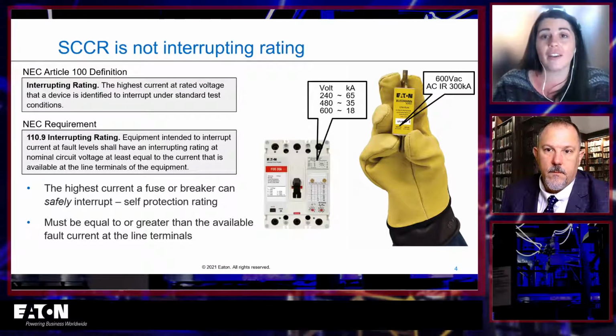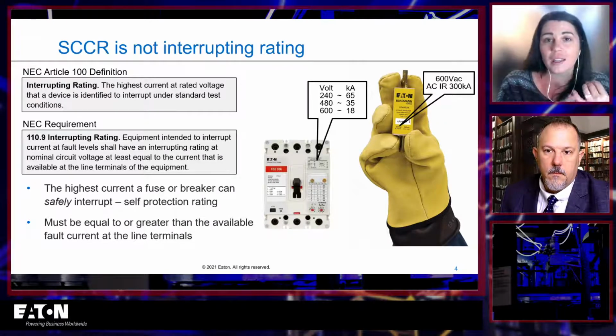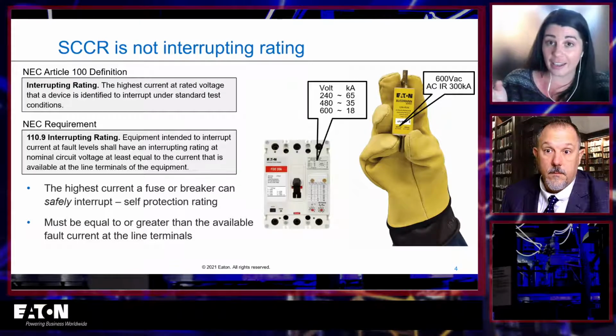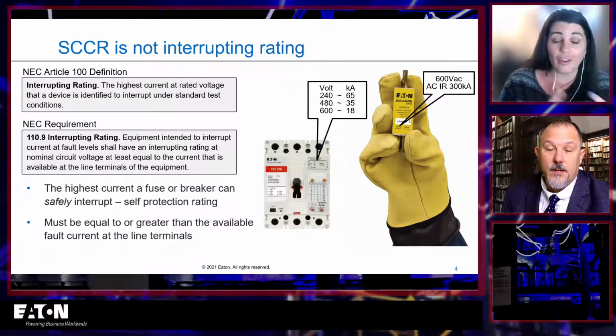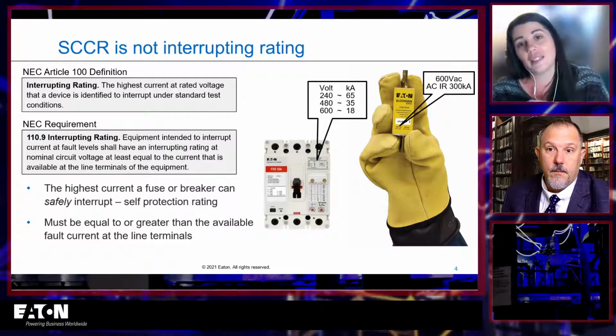Everything else, think of everything else in a panel. A bus, you think about a terminal block. What are they doing during a short circuit? They're sitting there waiting for a breaker or a fuse to open. So they're not interrupting anything themselves.